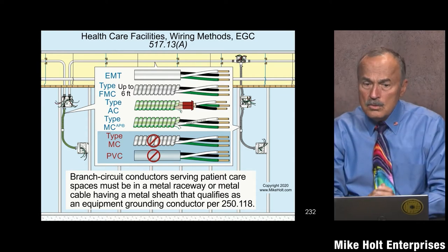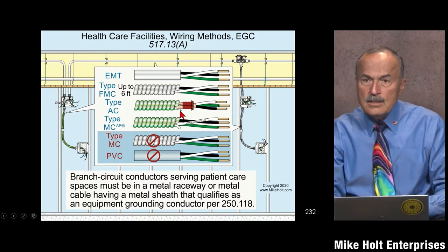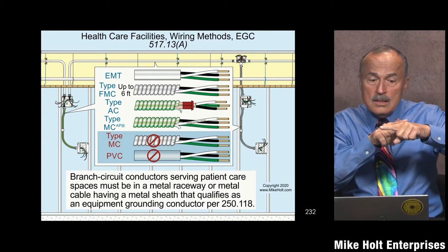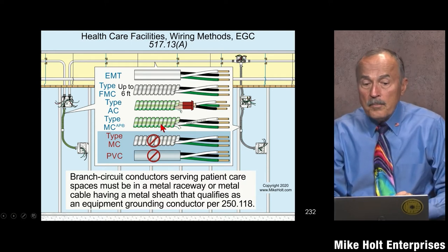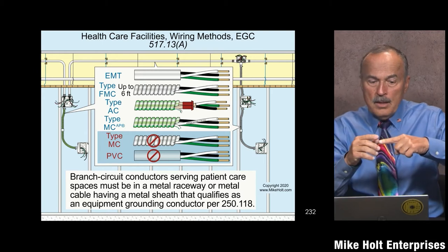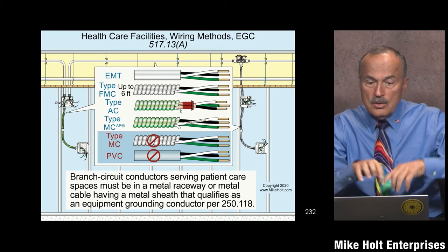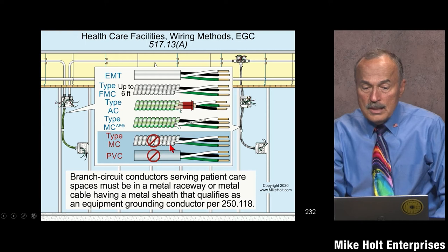Armor cable — not that common today — qualifies where it has an 16-gauge aluminum bonding strip, because that strip bonds each convolution to the next, making the armor sheath an effective ground fault current path. You can also use MC all-purpose and similar products with a 10-gauge aluminum bonding strip, where the wire connects each individual convolution — so the MC cable sheath of that type is an effective ground fault current path. Traditional MC cable without a bonding conductor does not qualify. And of course you can't run PVC.